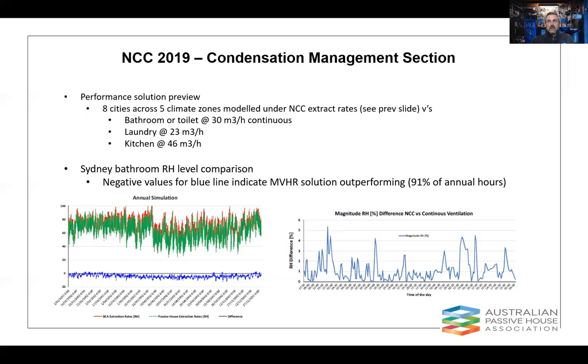And what you can see here clearly, for the vast majority of the time, in fact 91% of annual hours, we get better performance with an MVHR system than we do with a standard NCC system, with some reasonable assumptions about operation. On the right there, you can see a shorter term daily relative humidity. You can see the spikes there. Again, it's a difference between the 2, but you can see the spikes that relate to showers and things like that, but they rapidly are dehumidified and come back to the low levels.